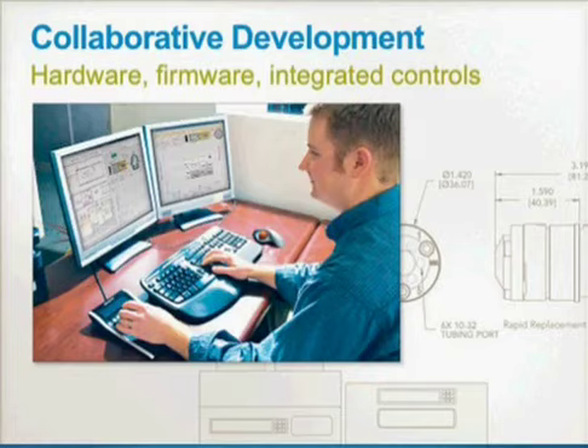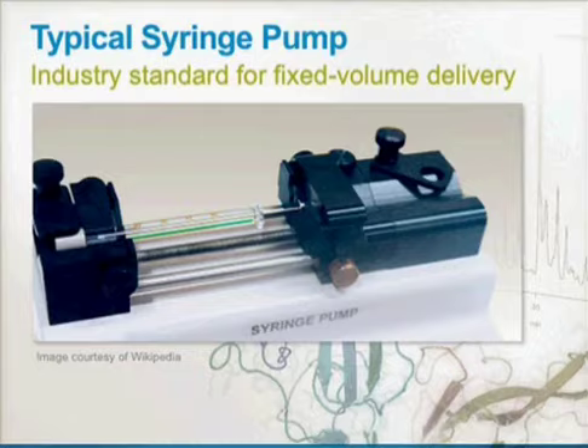Yeah, and I think that the real advantage that you got with this over syringe pump, and I think it's fair to say you wouldn't be able to do this with a regular syringe pump. Well, no, and so one of the hidden secrets with syringe pumps is that they're fantastic at delivering fixed volumes as long as you use the entire stroke of the syringe. But they're absolutely horrible in flow rate precision. For these sorts of applications, you get peak-to-peak variation of around 20% or so, and you just can't even imagine doing an experiment like this with technology like that.